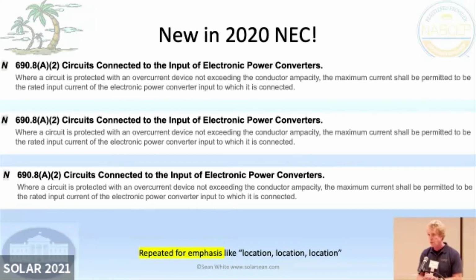But what we're doing now is we are oversizing our PV array. They call it clipping. So let's say that I had 2 megawatts of PV on a 1 megawatt inverter. That's an extreme example, but let's say I did that. Well, it's never going to take in more than a megawatt, or maybe a little bit more just for inverter inefficiency. Let's just say it's never going to take in more than a megawatt. So why do I have to size my wires for 2 megawatts? We're going to size it based on the input.